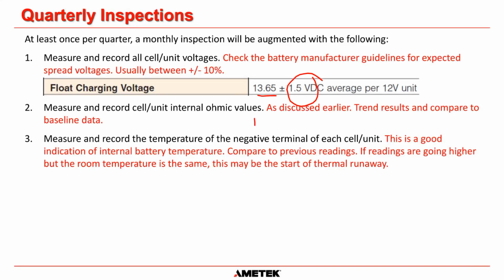That means you can go down to 12.5 volts and still be within an acceptable range, or you can go up to 15.2 volts. Okay, my math's terrible. It's a 3-volt spread basically, so that must be 15.5, something like that. So if the voltages of all the monoblocks are within that range, then you don't have to do anything. Everything is okay. It's only when they go out of that range that you have to consult the battery manufacturer's guidelines, and they may recommend that you do an equalize charge, and you have to follow the parameters that the battery manufacturer stipulates.